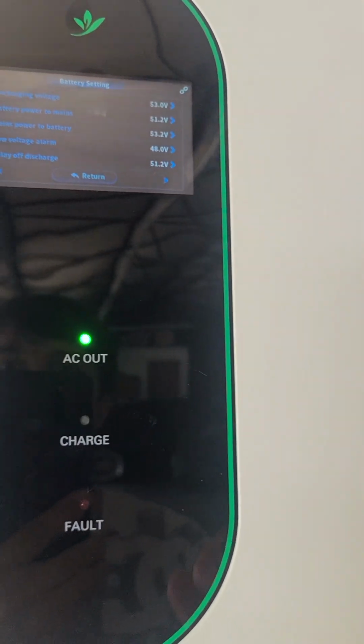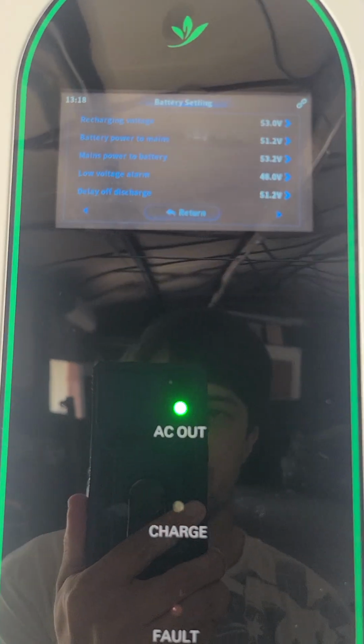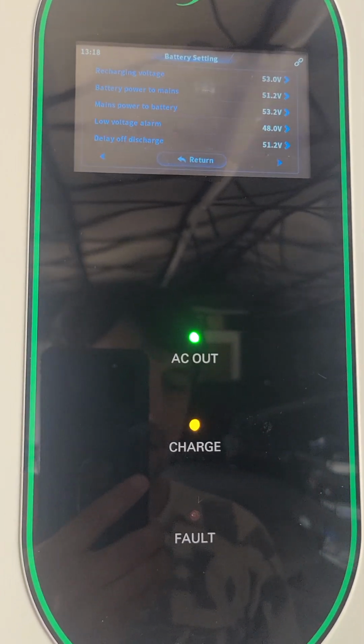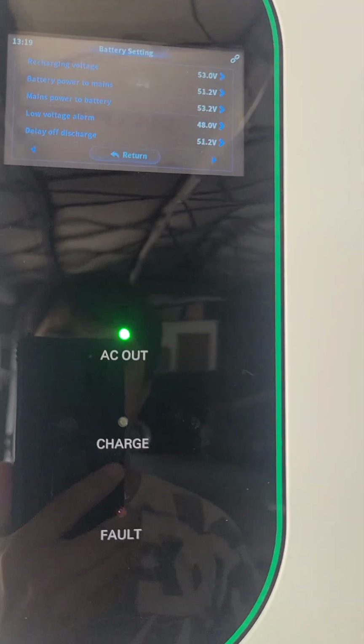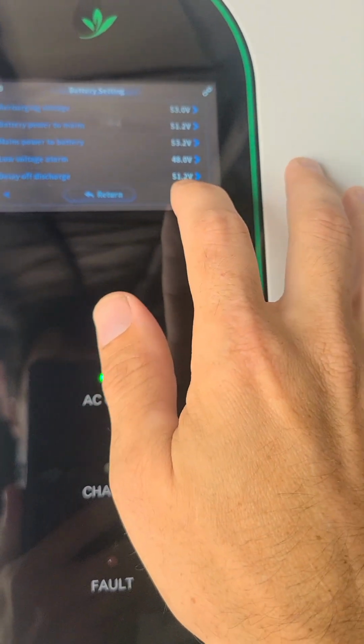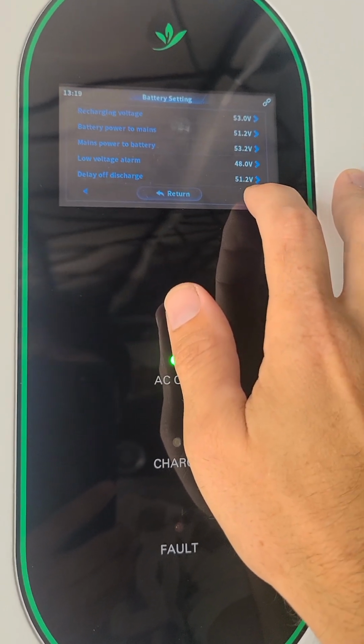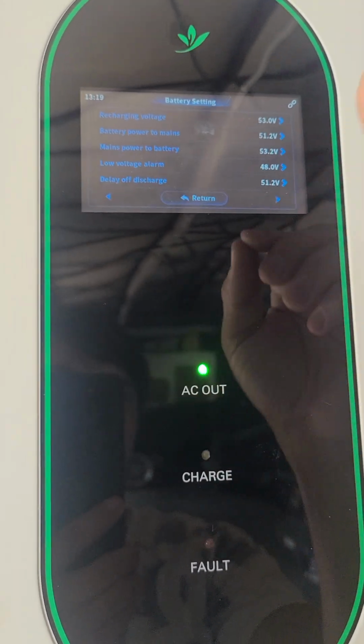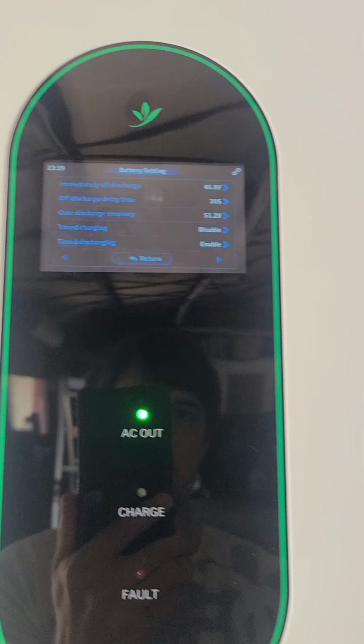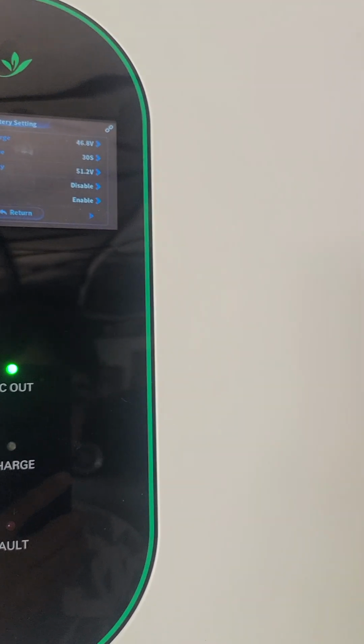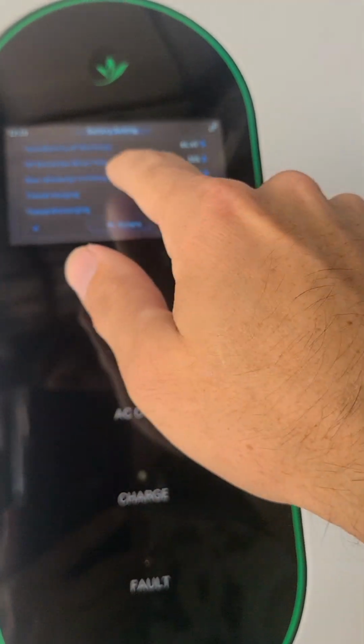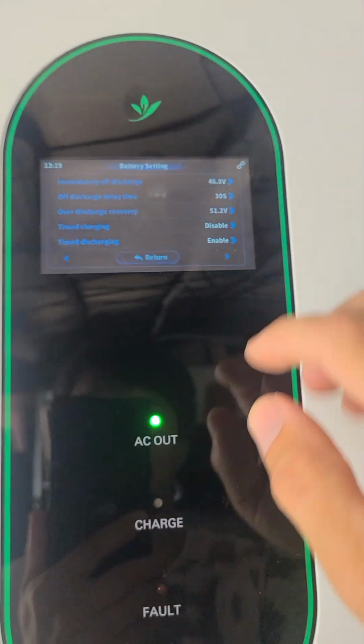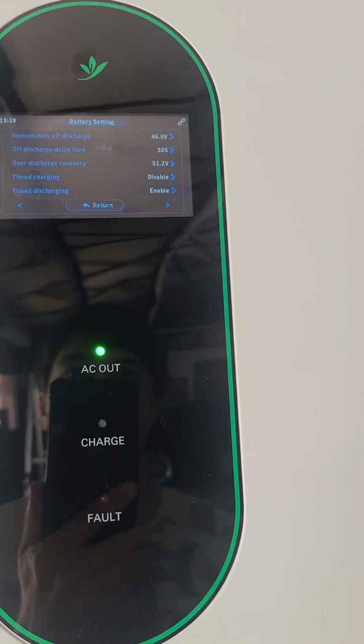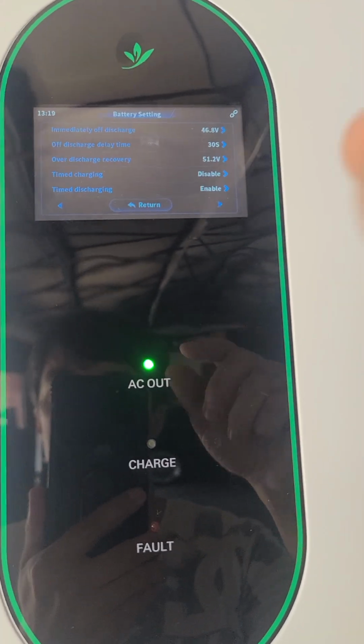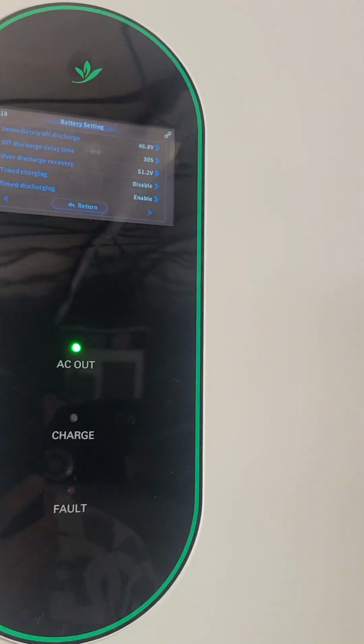Then we got the low voltage alarm at 48 volts. That's about 15% battery. Now the delay off discharge, this matters because off discharge means we're going to stop discharging the battery, and we're going to do it after a delay. So at 20% capacity, we're going to stop discharging the battery if we are below that voltage for long enough. Now immediately off discharge, that's like 10%. So if we get that low, we're just going to shut it off immediately. Now off discharge delay time, that means that we turn off the discharge on the other setting on a delay of 30 seconds is what I set it to. And then over discharge recovery, if we get above 20%, we can resume discharging the battery. Now here's where the zero export runs into issues with people not understanding the naming nomenclature.